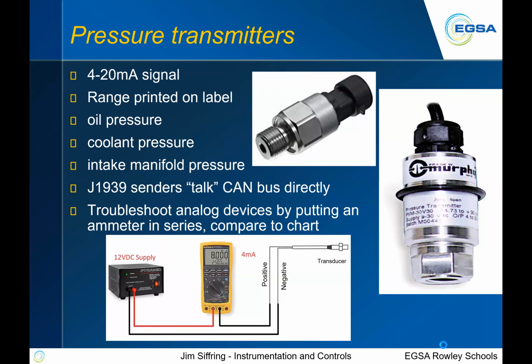So say at low pressure, maybe at 0 psi, it's going to flow 4 milliamps through it. And let's just say the high end is 100 psi, at 100 psi, it would flow 20 milliamps. And with the remaining 16 milliamps between the 4 to 20, you can scale that, so at 50 psi, you'd see 12 milliamps of current flow. Those ranges are typically printed on the label itself. You see on the right hand side, you can see that the range is printed on there.